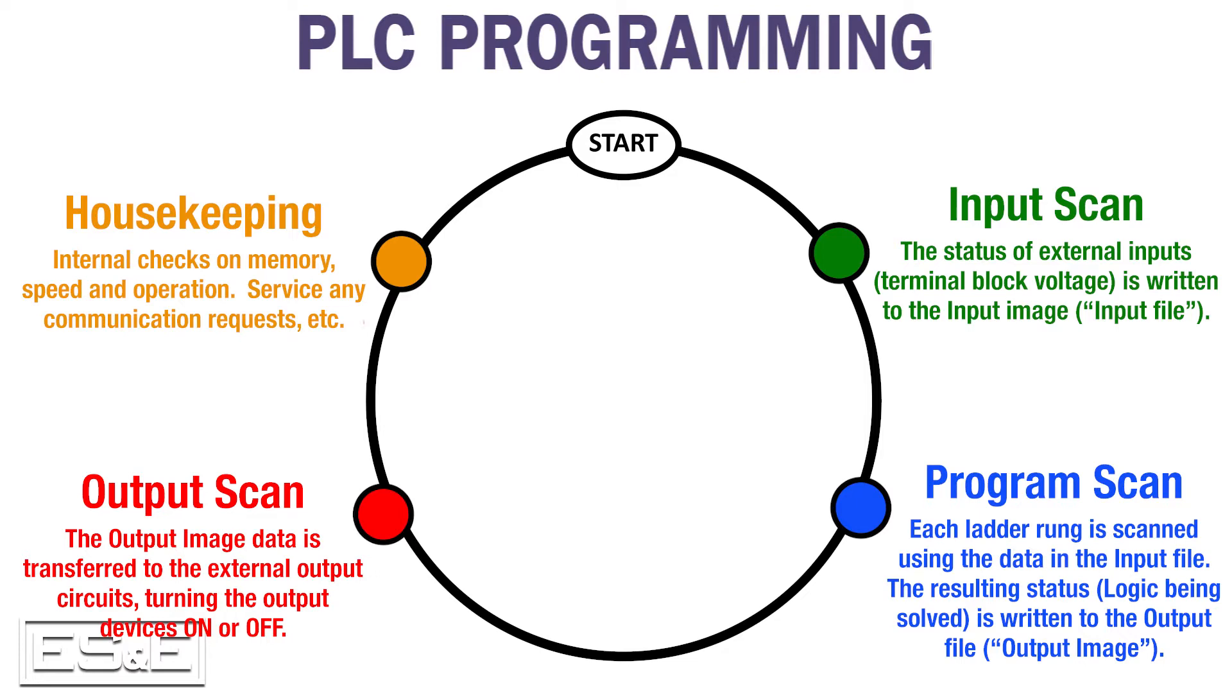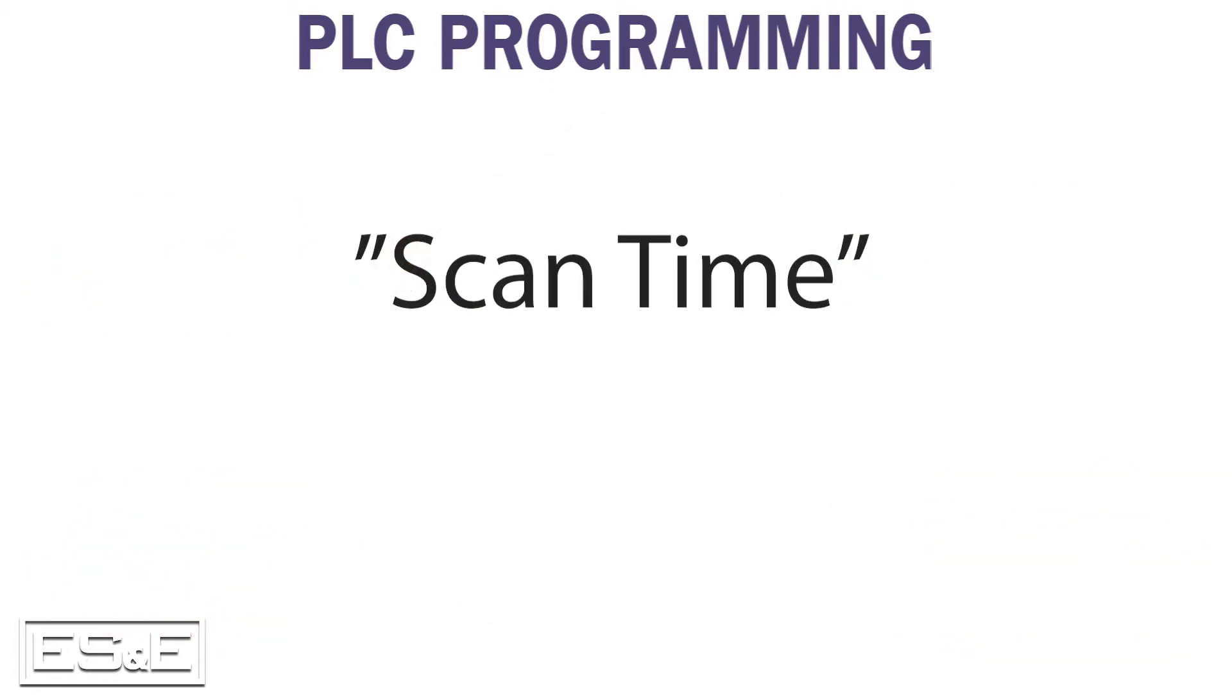The amount of time it takes for the PLC to go through this cycle is referred to as scan time. Depending on the size of the program and the age of the technology, scan times are typically measured in milliseconds. Newer technology has driven scan times down to microseconds for the equivalent size programs.